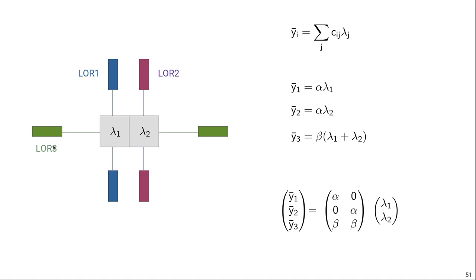Since we know the acquisition physics very well, we can perfectly describe the system in terms of equations. If we know the activity concentration in voxel 1 and 2, we can perfectly describe the expected measurements on the three LORs. In this example, LOR 1 is only sensitive to voxel 1, so the expected measured value on LOR 1 is alpha times lambda_1. LOR 2 is only sensitive to activity in voxel 2. And LOR 3 gets contributions from both voxels, lambda_1 and lambda_2, with a sensitivity factor beta.